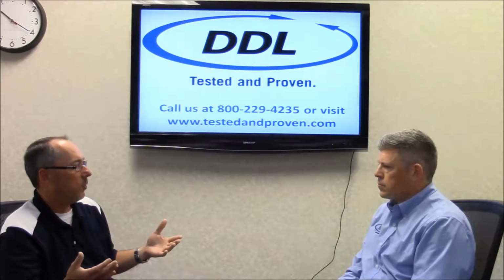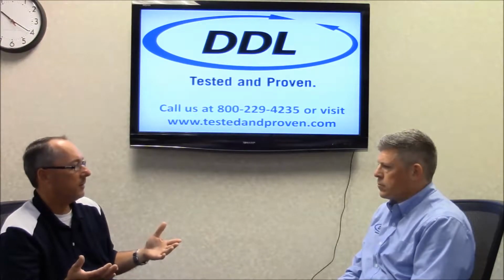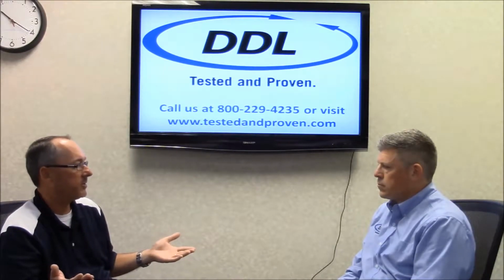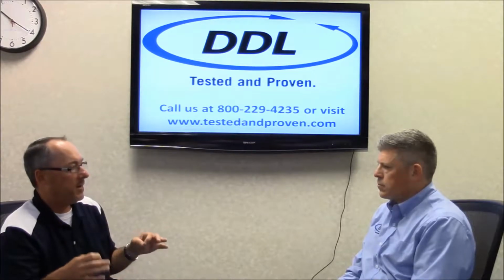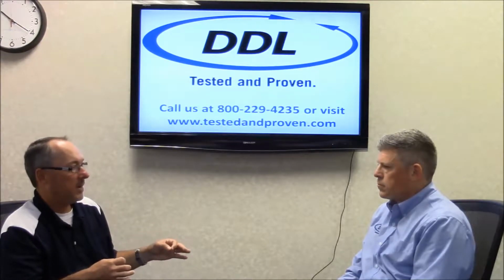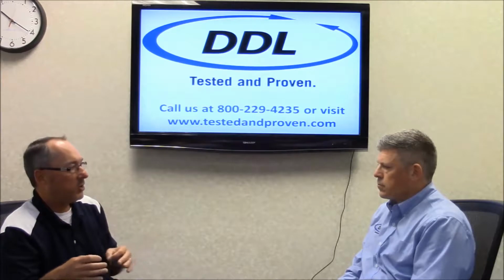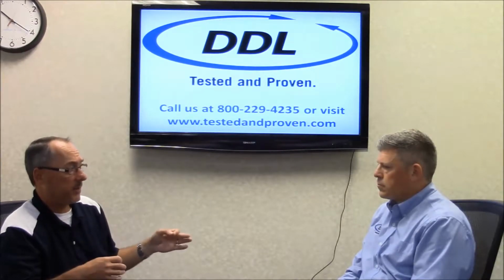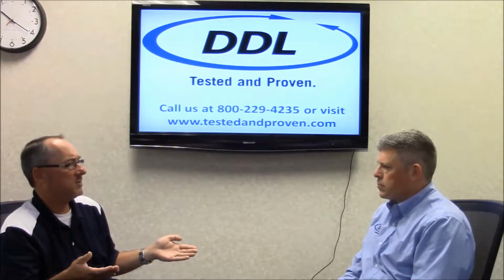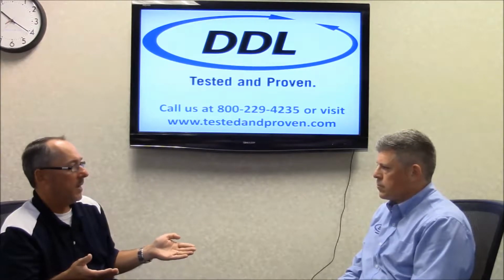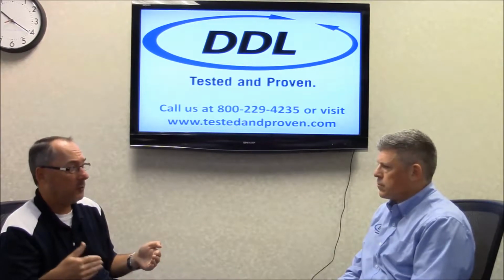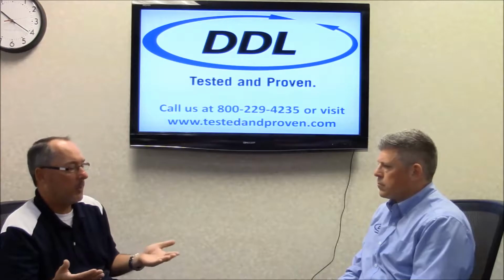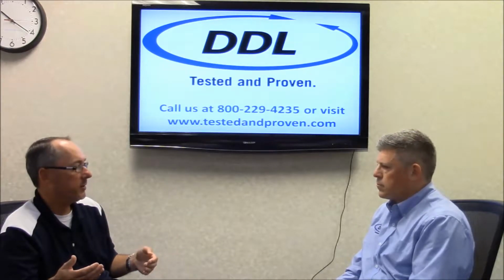Typically DDL as a whole, we go less than 20%. On average, we're sitting about 9 to 10%. But the key thing to keep in mind is you want as low as absolute possible. If you elevate your relative humidity with an elevated test temperature, let's say you're at 55 at 60% relative humidity, and if you look at the parts per million or the absolute moisture content, you're probably over 100% saturation rate.